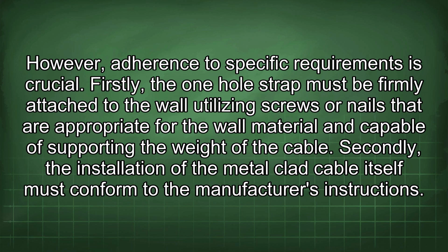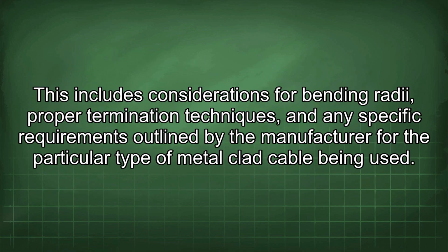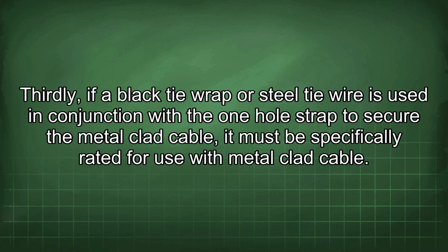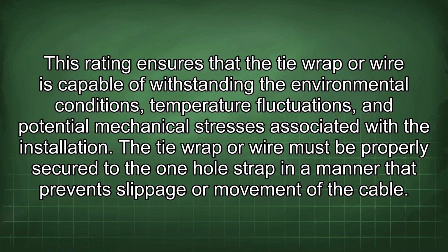Secondly, the installation of the metal-clad cable itself must conform to the manufacturer's instructions. This includes considerations for bending radii, proper termination techniques, and any specific requirements outlined by the manufacturer for the particular type of metal-clad cable being used. Thirdly, if a black tie wrap or steel tie wire is used in conjunction with the one-hole strap to secure the metal-clad cable, it must be specifically rated for use with metal-clad cable. This rating ensures that the tie wrap or wire is capable of withstanding the environmental conditions, temperature fluctuations, and potential mechanical stresses associated with the installation.